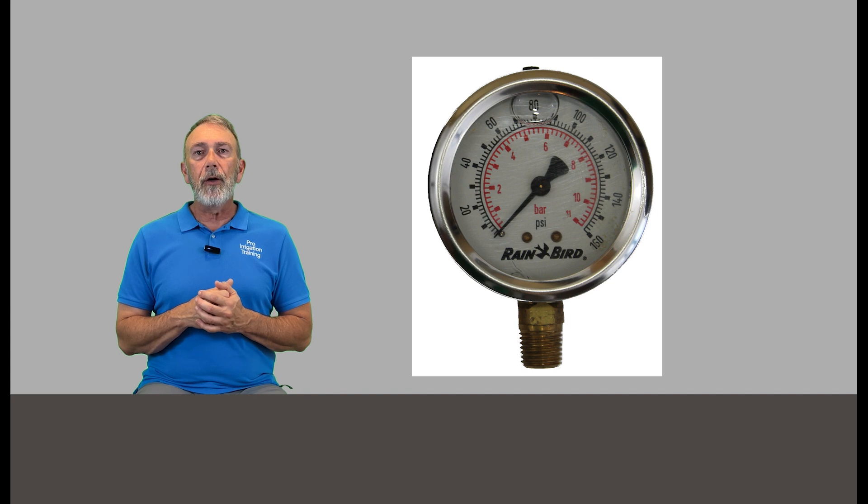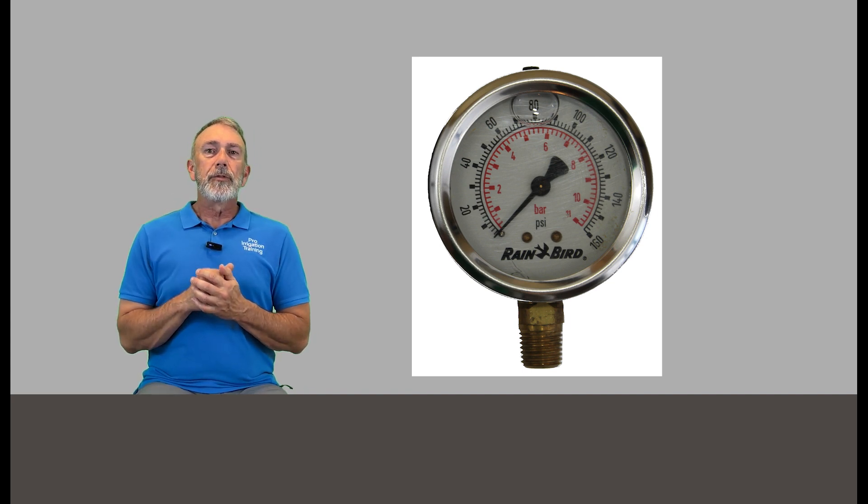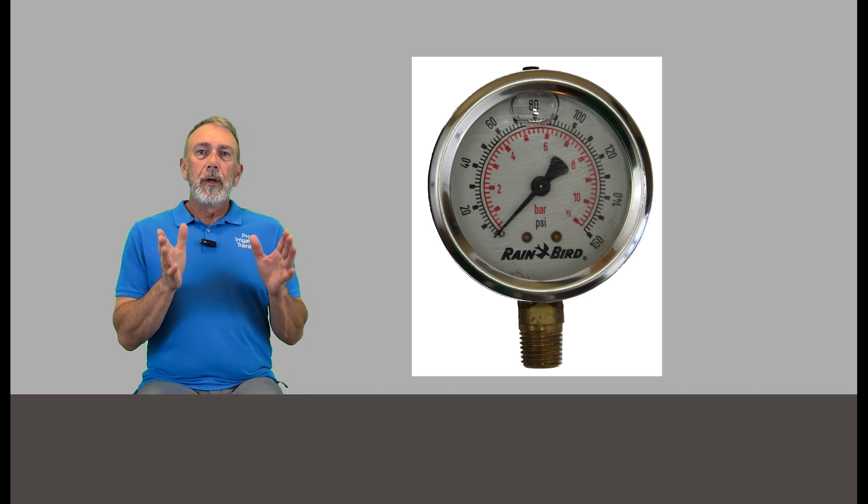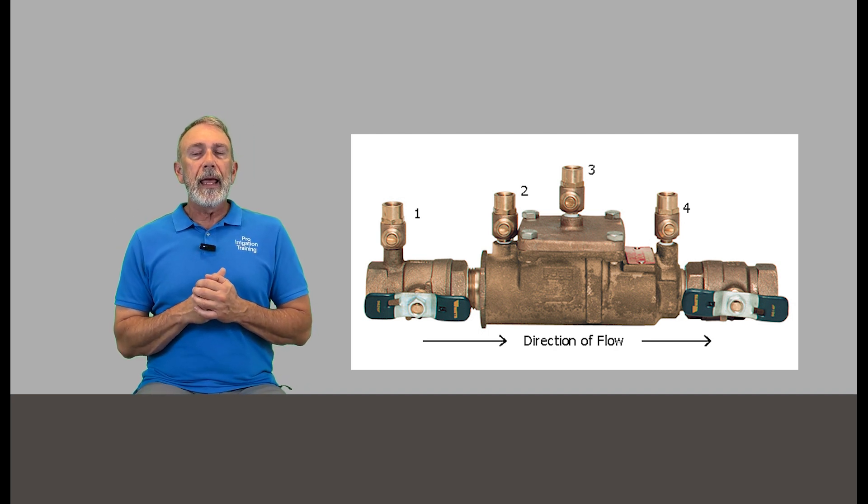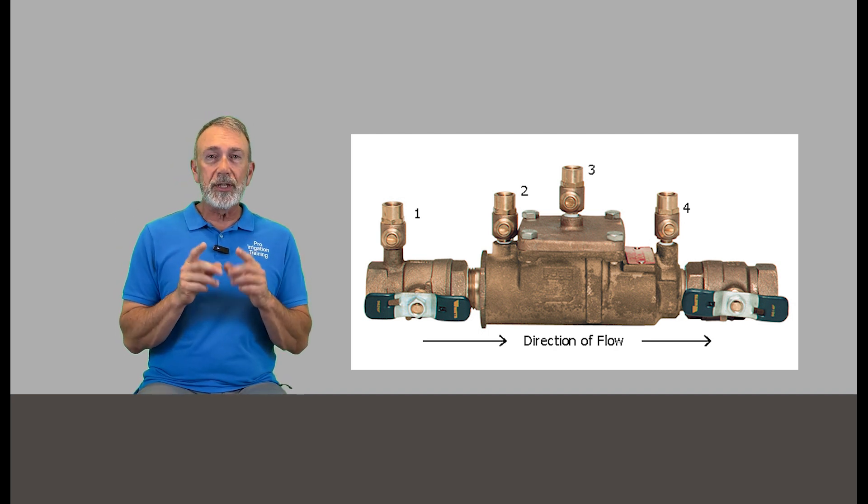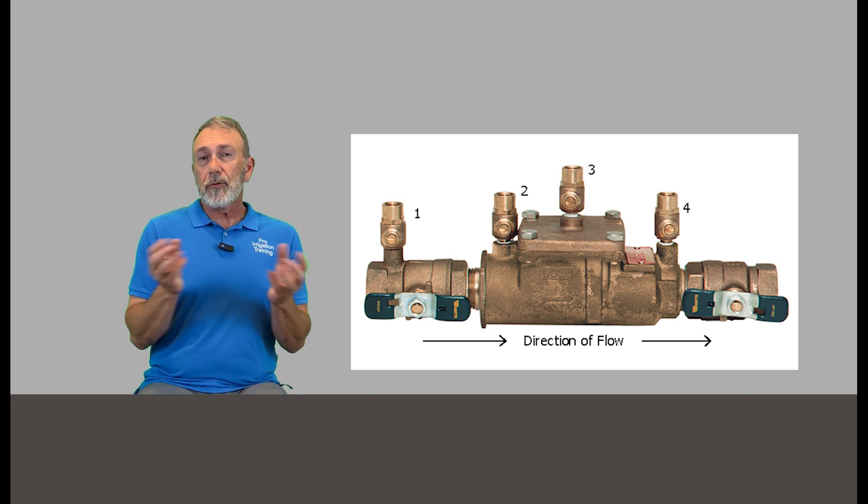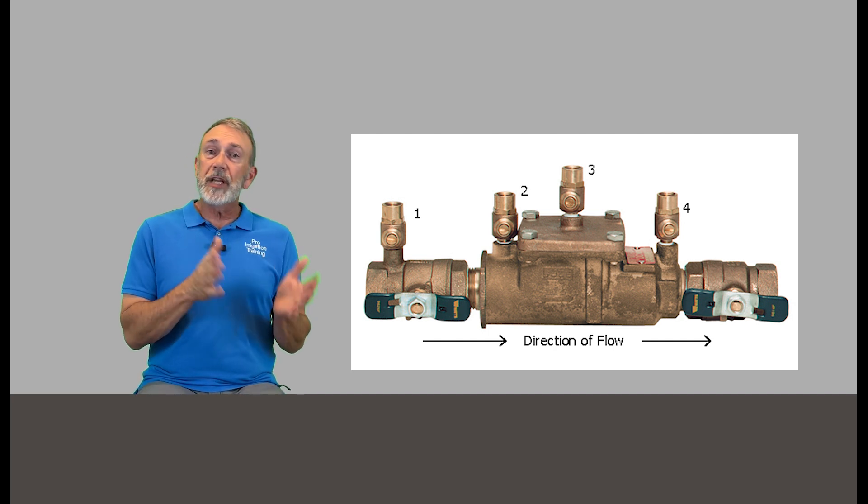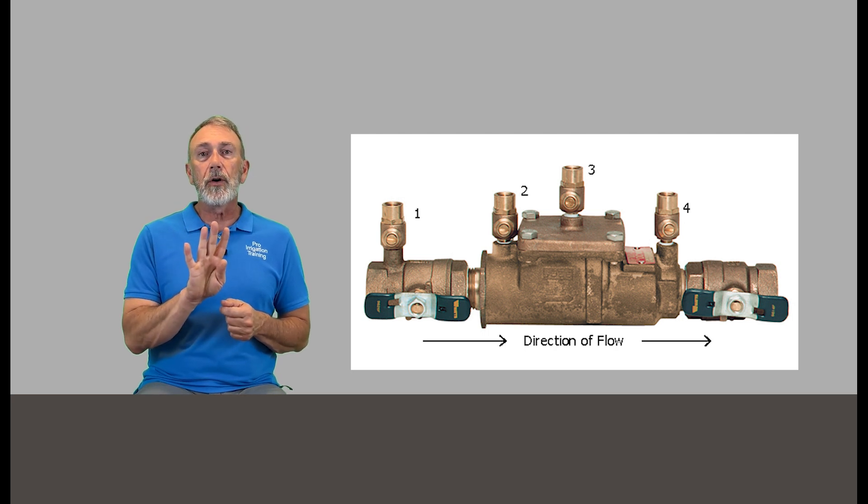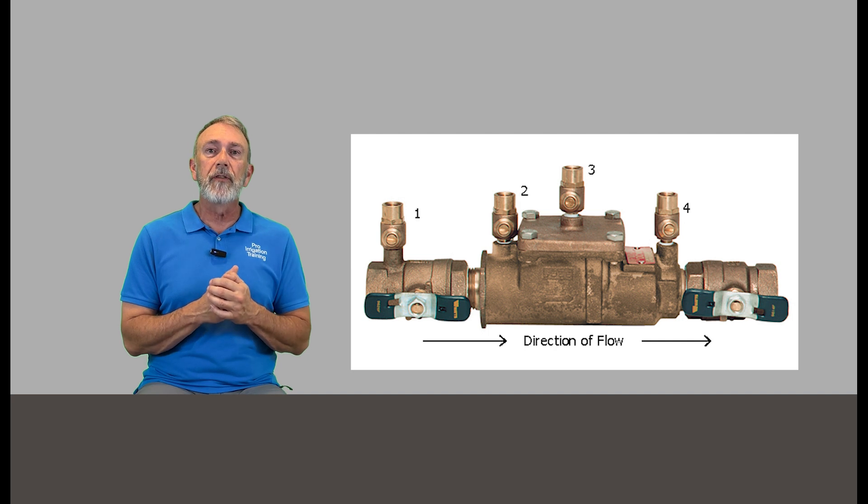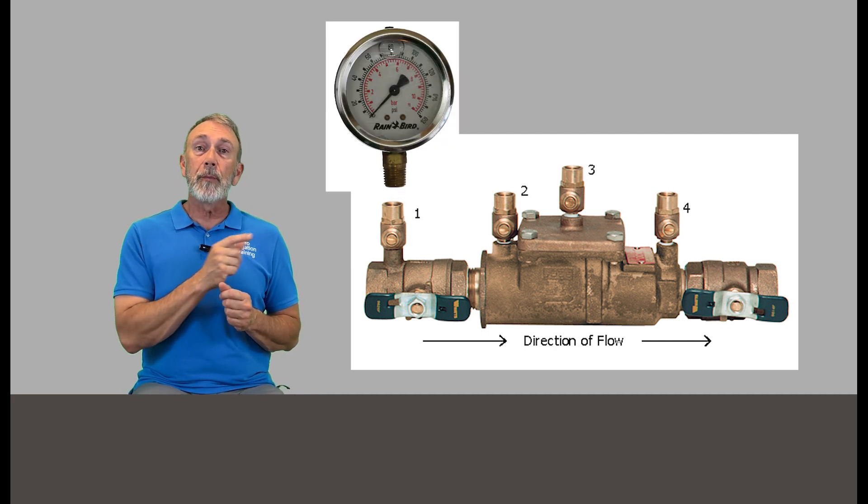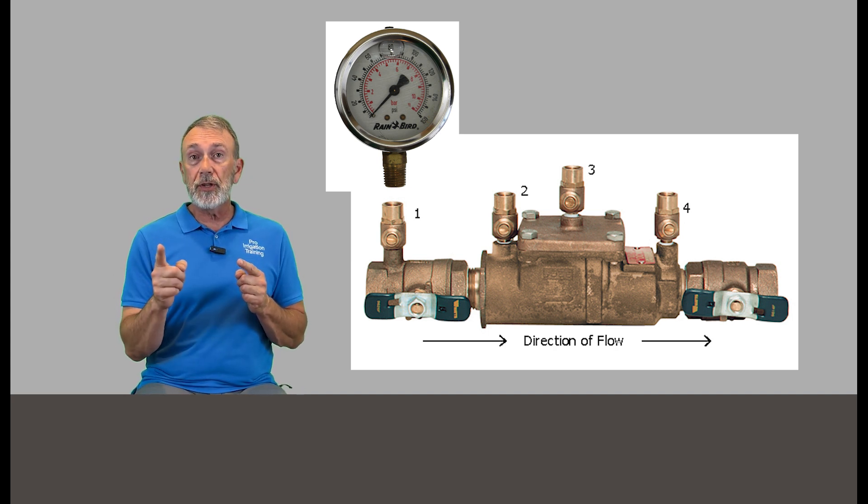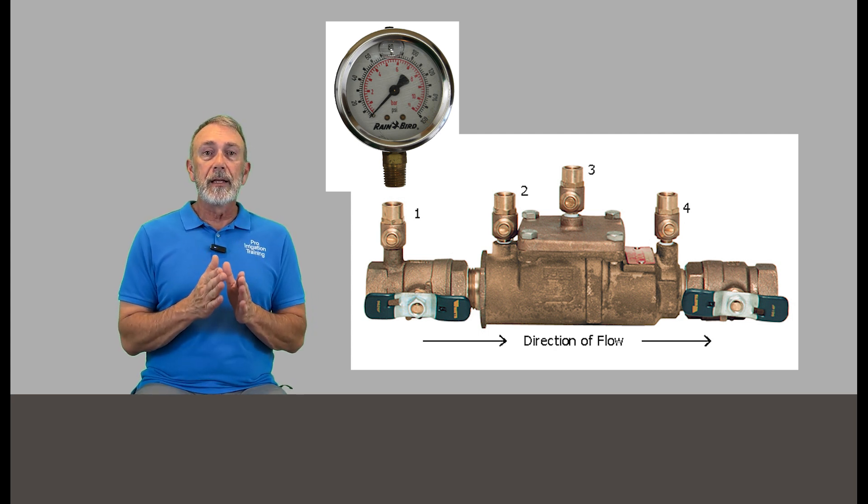Go to your truck and get a pressure gauge out, one with like a three eighth inch thread on it that fits into the test cocks on the backflow preventer. We're going to get our pressure gauge and then go to the backflow preventer. Unless it's a residential dual check, which has no test cocks, it's not testable, it's not repairable. You have to replace it or just replace the guts on it. But if we have a double check valve assembly or reduced pressure principal assembly, these have four test cocks on them. And there's other kinds that just have two test cocks, but you can tell across the device if there's a problem.